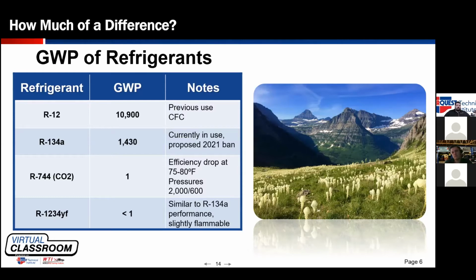1234YF in original testing was found to have a global warming potential of 4. Current research has found it to have a GWP of less than 1. So it is less likely than CO2 to contribute to global climate change. As technicians, as far as fixing a system, it works very similar to R134A. Similar performance, with some slight changes to the systems to improve performance. The downside is it is mildly flammable. It is called an A2L refrigerant. That means that if you expose it to an ignition source, it will ignite, but it will not sustain a flame if that ignition source is taken away.